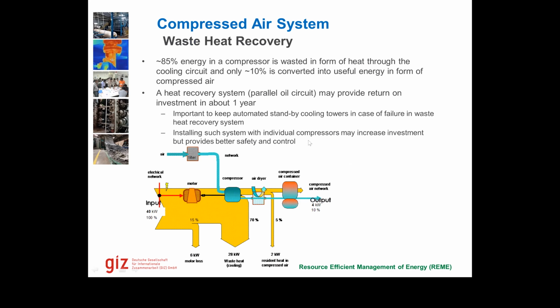So a compressed air system typically provides up around 10 to 13% efficiency in total. Most of the energy is going into waste heat, which is the cooling circuit. In the areas which are colder, heat recovery from this system also becomes feasible. But if we are living in hot areas, the heat recovery might not bring in so many fruits.